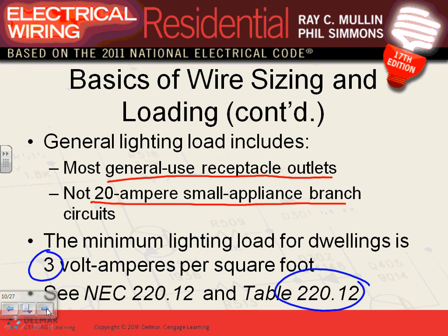Give me another not dishwasher. If you have a garbage disposal, it's not counted for garbage disposal. It doesn't count for dishwasher, doesn't count for dryers, doesn't count for range. See these equipment? These are allocated equipment, they're all loads. It also doesn't count for the 2 small appliance circuits in the kitchen that we're going to talk about in a second, as well as the bathroom. These have their own calculation. Other than that, everything is calculated within this 3 volt amp.